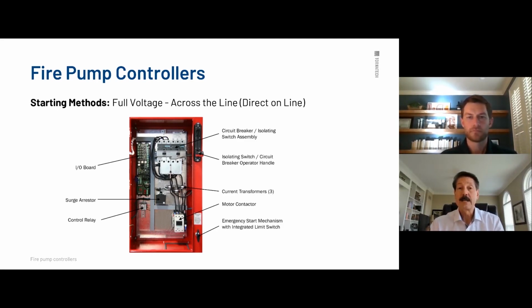And if it's a 208 volt, you're literally doubling the full load amperage, and in most cases, the current carrying components will double in size too. Definitely want to start looking at using a reduced voltage on a lower horsepower motor if you're actually attached to 208 volt.